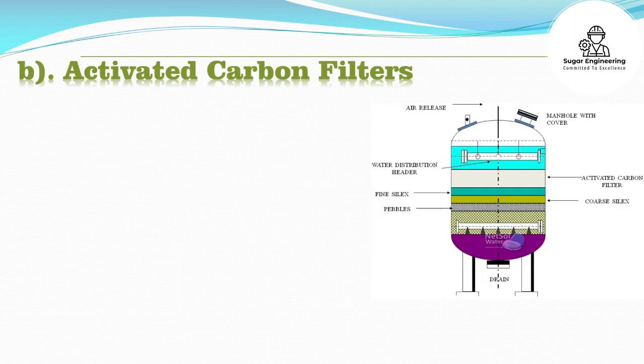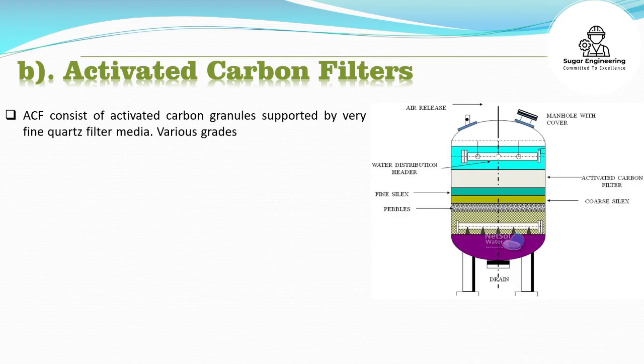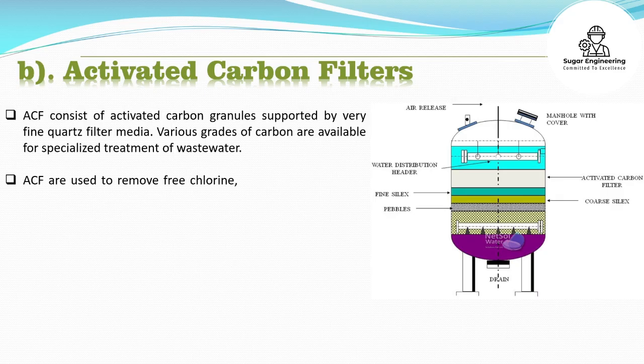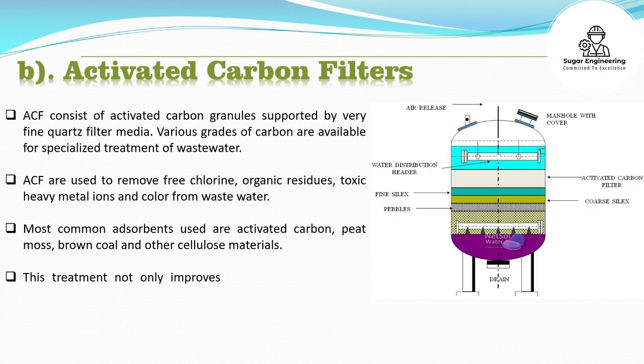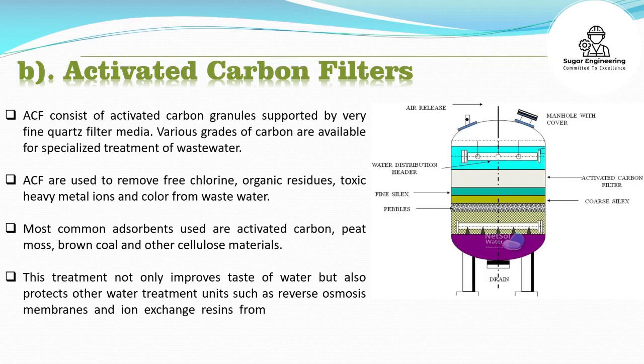Activated Carbon Filters (ACF) consist of activated carbon granules supported by very fine quartz filter media. Various grades of carbon are available for specialized treatment of wastewater. ACF are used to remove free chlorine, organic residues, toxic heavy metal ions, and color from wastewater. Most common adsorbents used are activated carbon, peat moss, brown coal, and other cellulose materials. This treatment not only improves taste of water but also protects other water treatment units such as reverse osmosis membranes and ion exchange resins from possible damage due to oxidation or organic fouling.